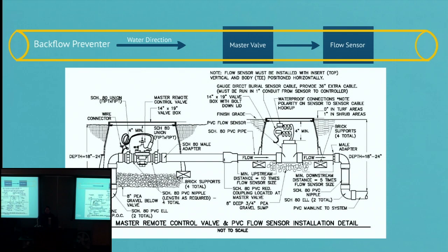Okay, as far as what you can see during installation, it's okay to go out on the site and look at the master valve while you're doing water coverage. You don't necessarily have to be there during installation, but on the flow sensor, because of the lengths of pipe, you'd have to be out there during installation to make sure the contractor has done the correct lengths before and after the flow sensor.